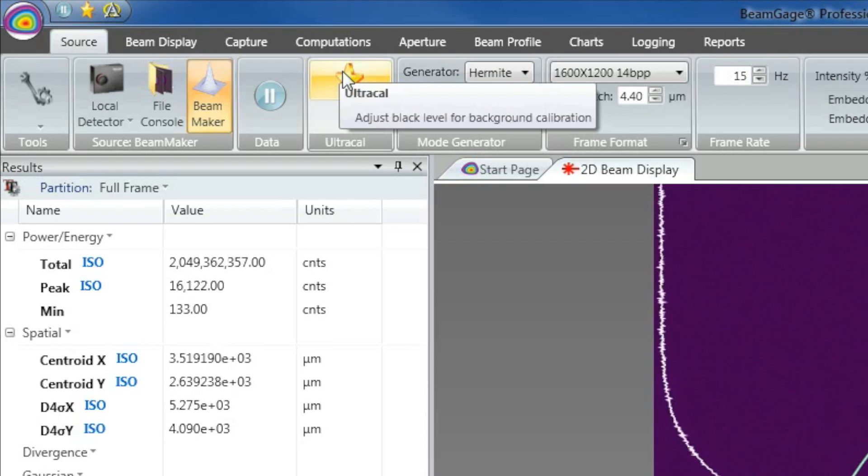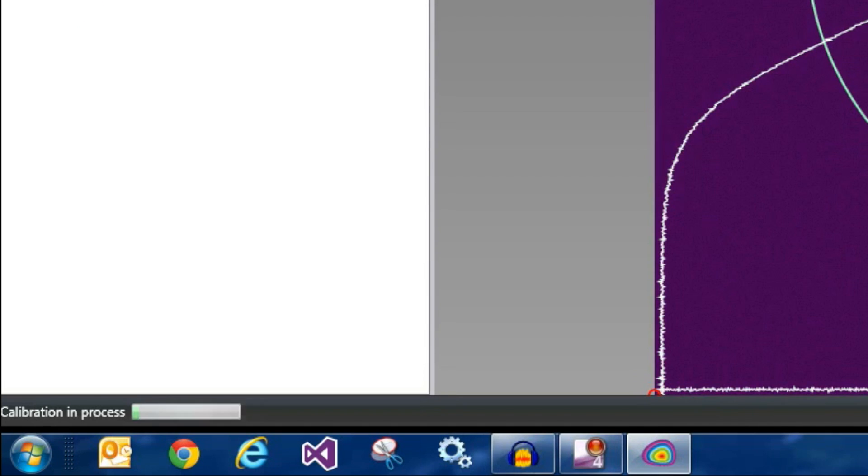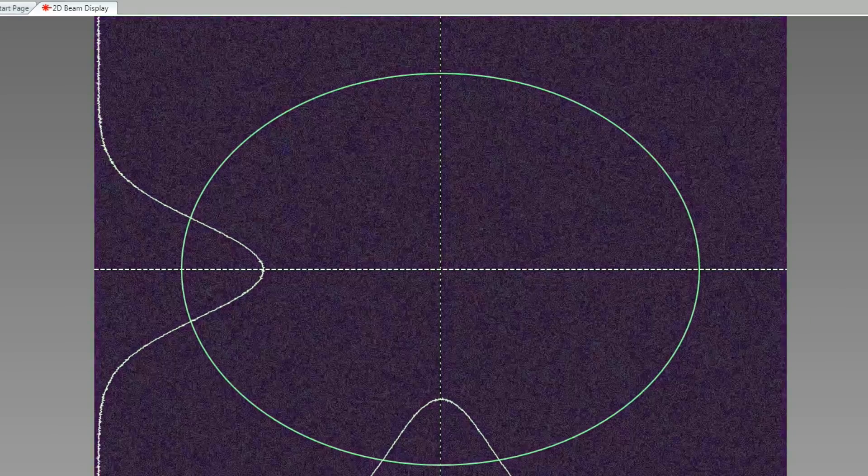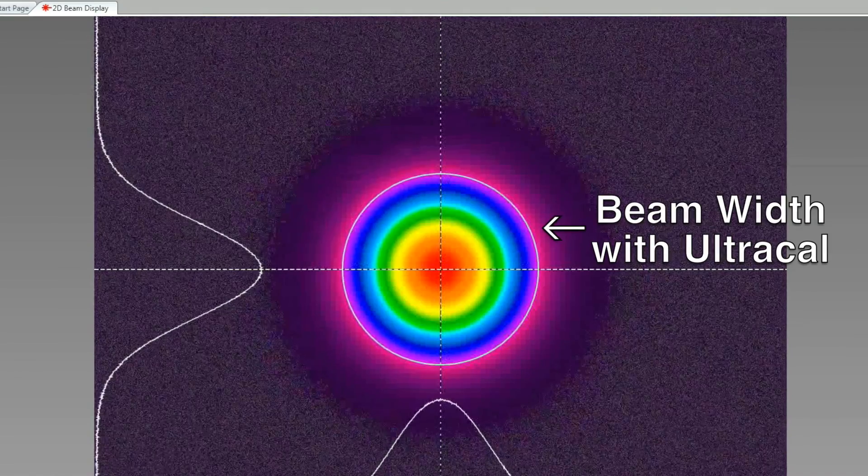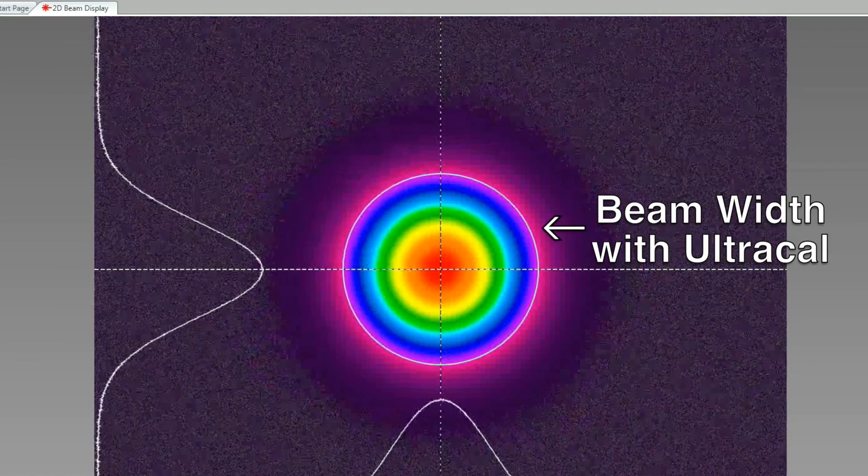Let's see how UltraCal improves our beam width calculation. We start by clicking the UltraCal button. BeamMaker blocks our beam, then collects sample data and calculates the baseline with the noise removed from each pixel. BeamGage now calculates the accurate beam width without system noise.